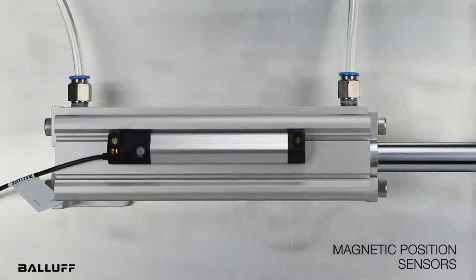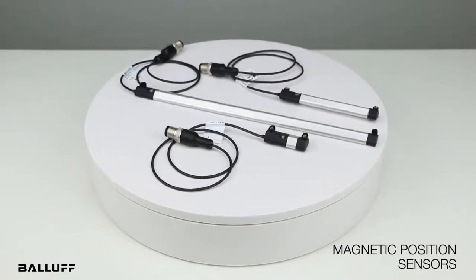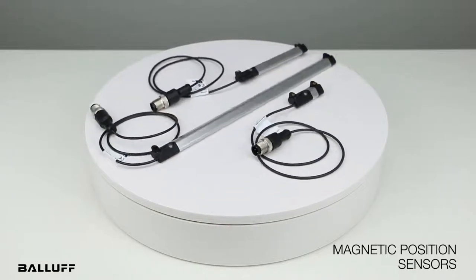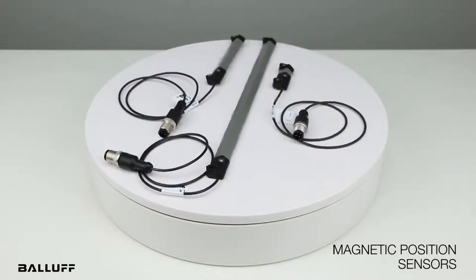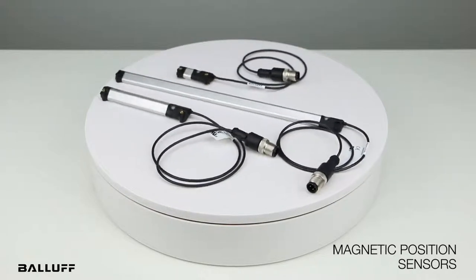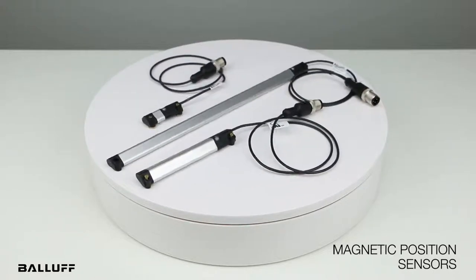The BMP Magnetic Position Sensors are available in eight different measurement ranges from 32 to 256 millimeters in 32 millimeter increments. You can also customize the measuring range along the entire stroke using the TEACH function. Each size comes with three options for connections, giving you 24 variants to choose from for your specific needs.